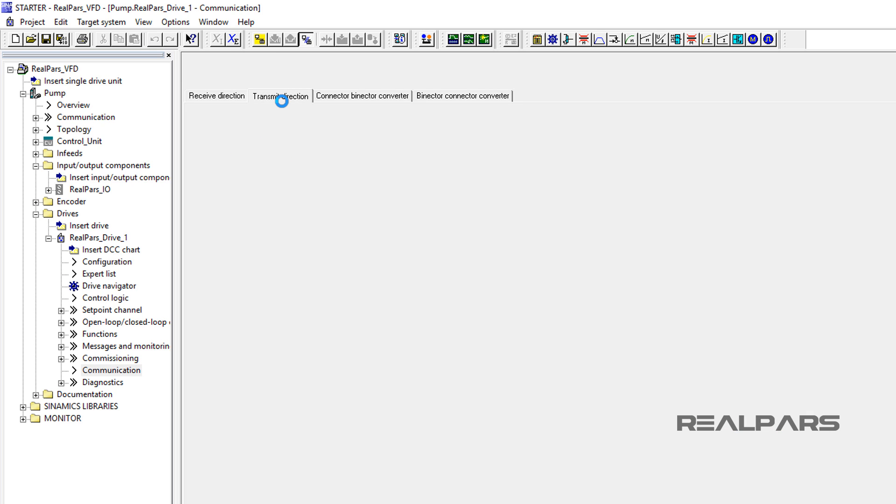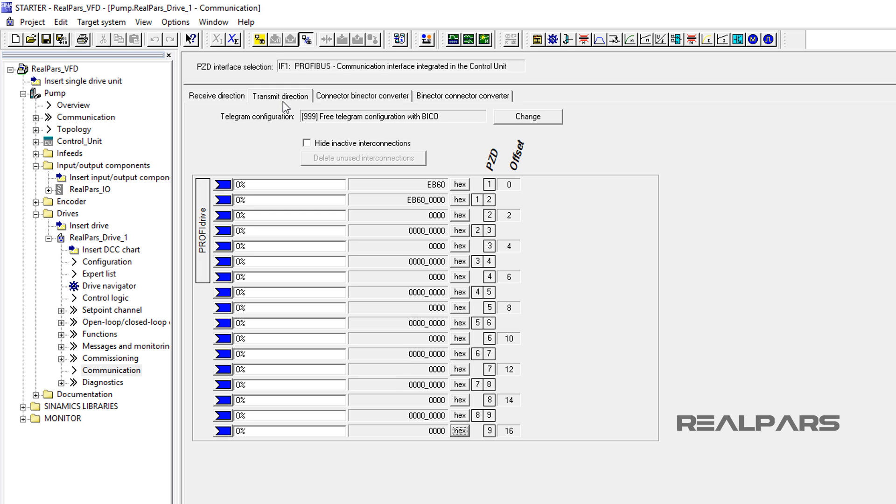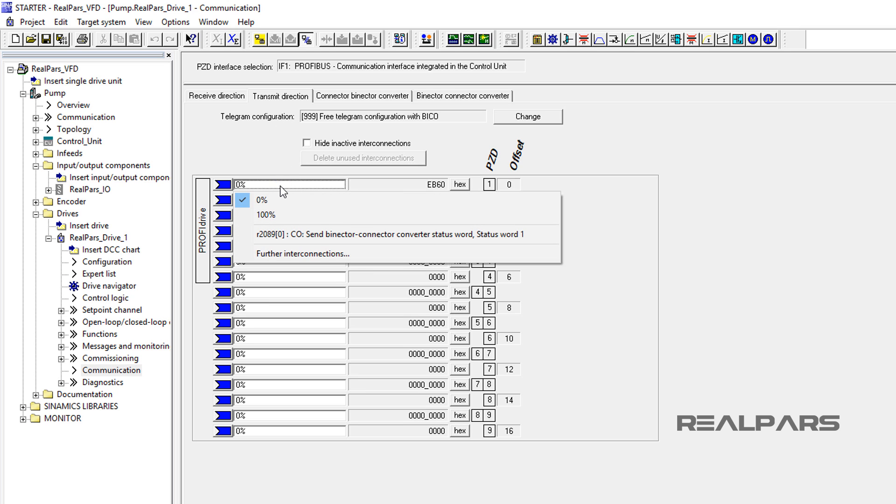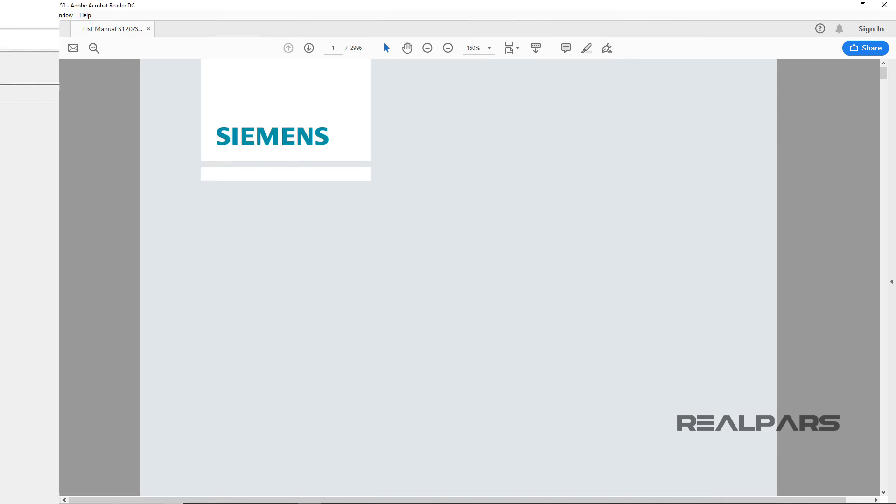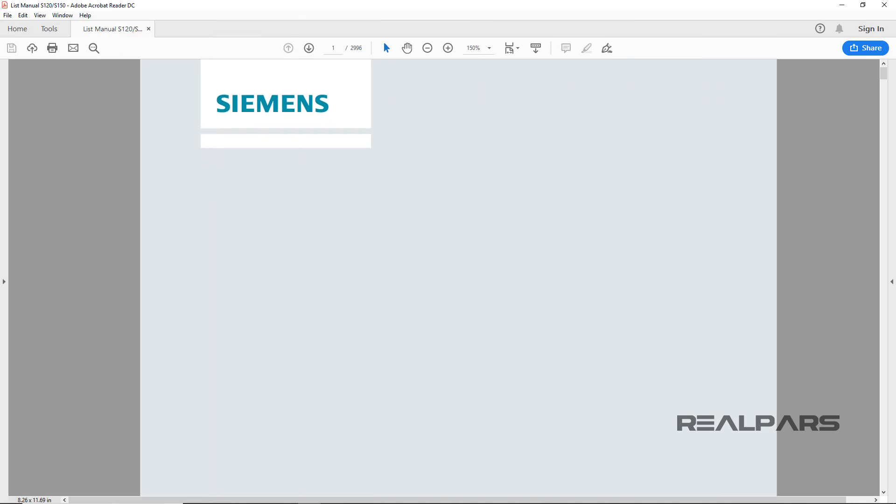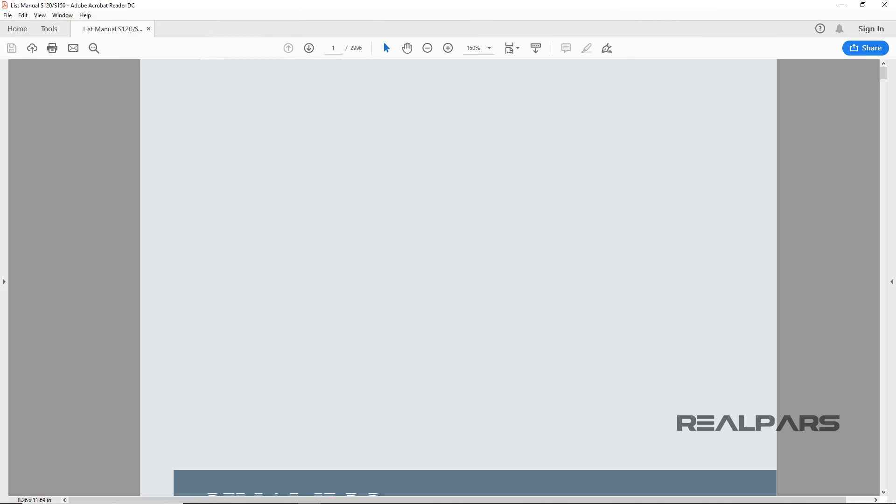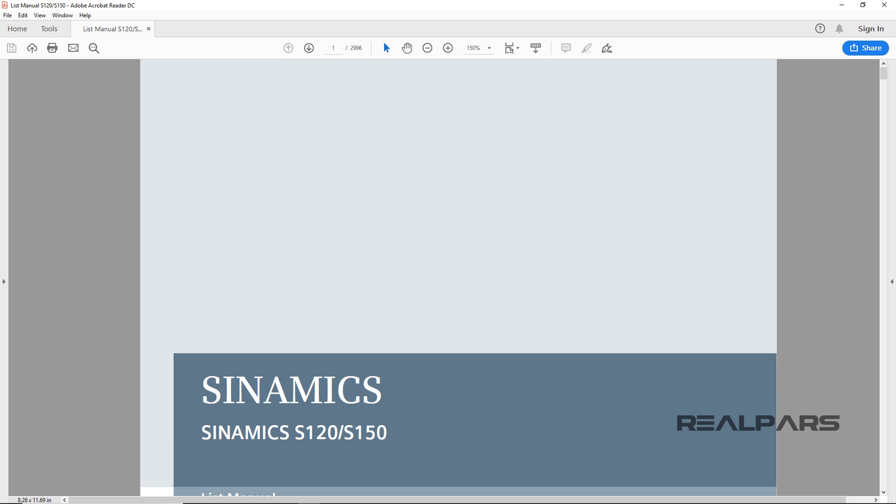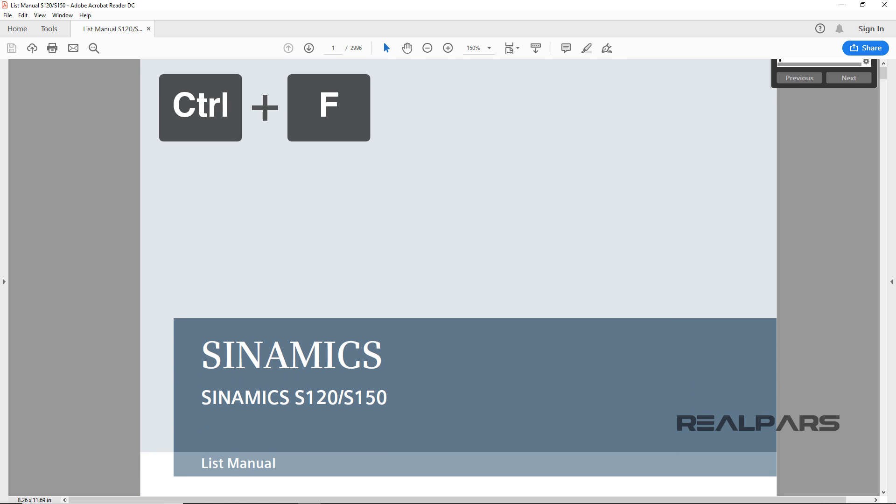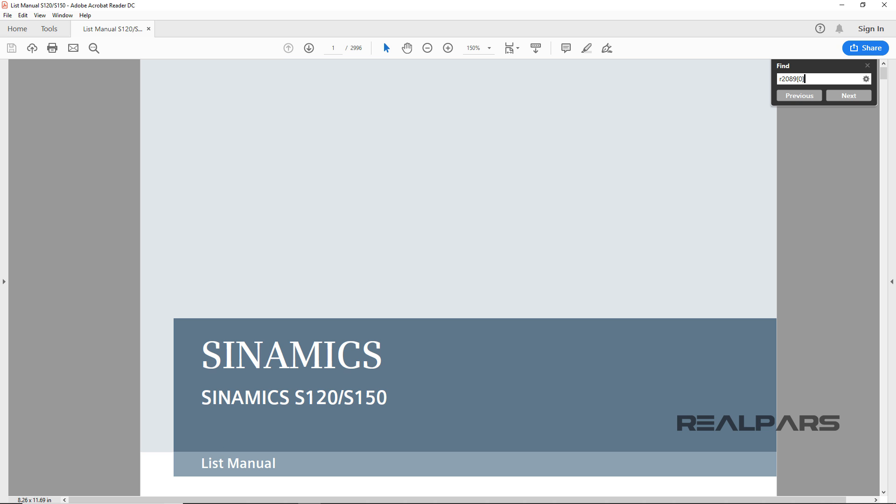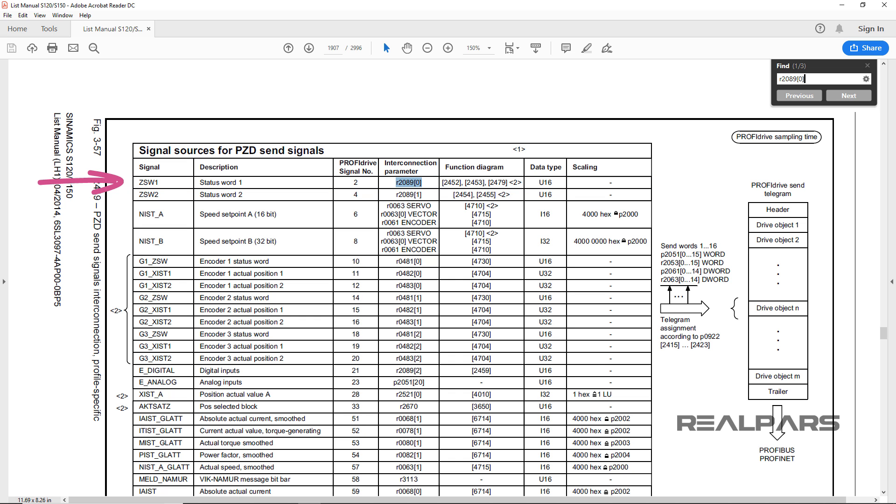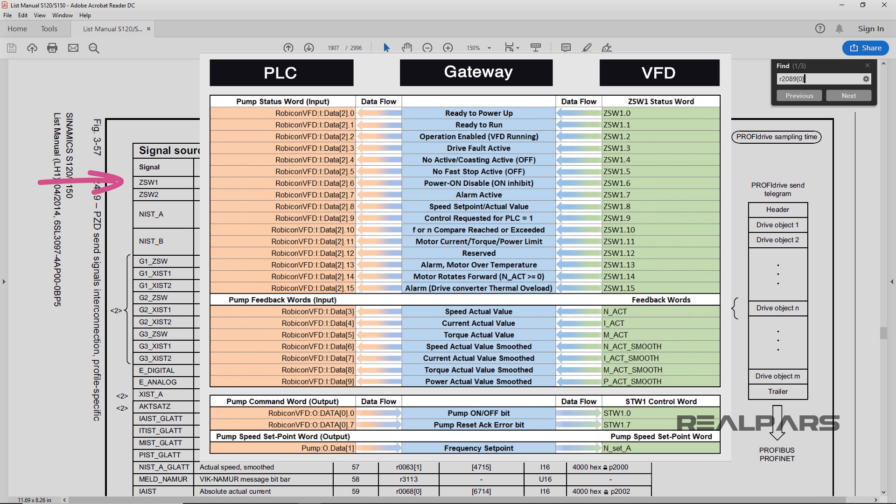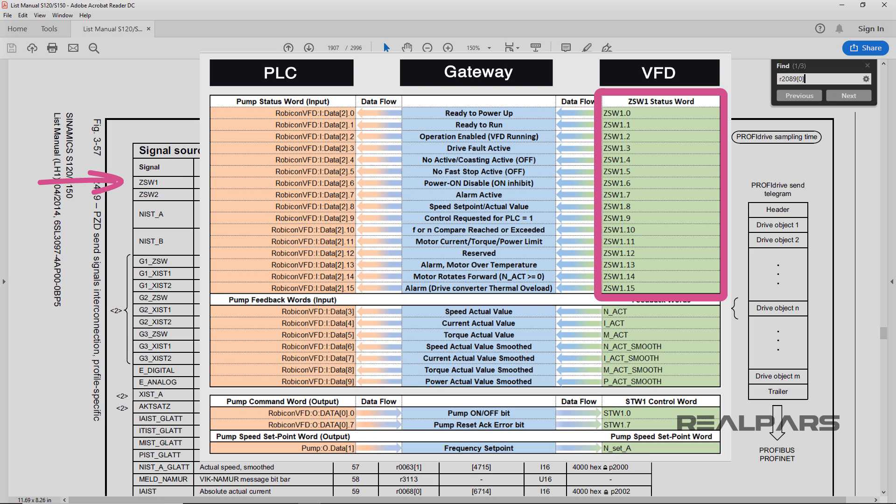Next, under the Transmit Direction tab, I will enter a few more parameters. First, I click into the PZD1, then I locate r2089[0], the Send Binector Connector Converter Status Word, Status Word 1, and select it by clicking on it. If you open the Sinamics S120/S150 parameter manual and search for the r2089[0], you will find out where the ZSW word naming derives from. From previous parts of this video series, you can remember the ZSW1 status words in the spreadsheet, which were sent from the Siemens VFD toward the Rockwell PLC via the HMS Anybus Gateway.